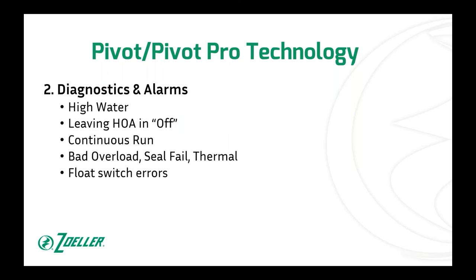Second, diagnostics and alarms. You have a high water alarm, an alarm for leaving the HOA in off, a continuous run alarm, alarms for bad overload, seal fails, thermals, and float switch errors like a logical fault. All of these are built right in — you're not paying extra for them.